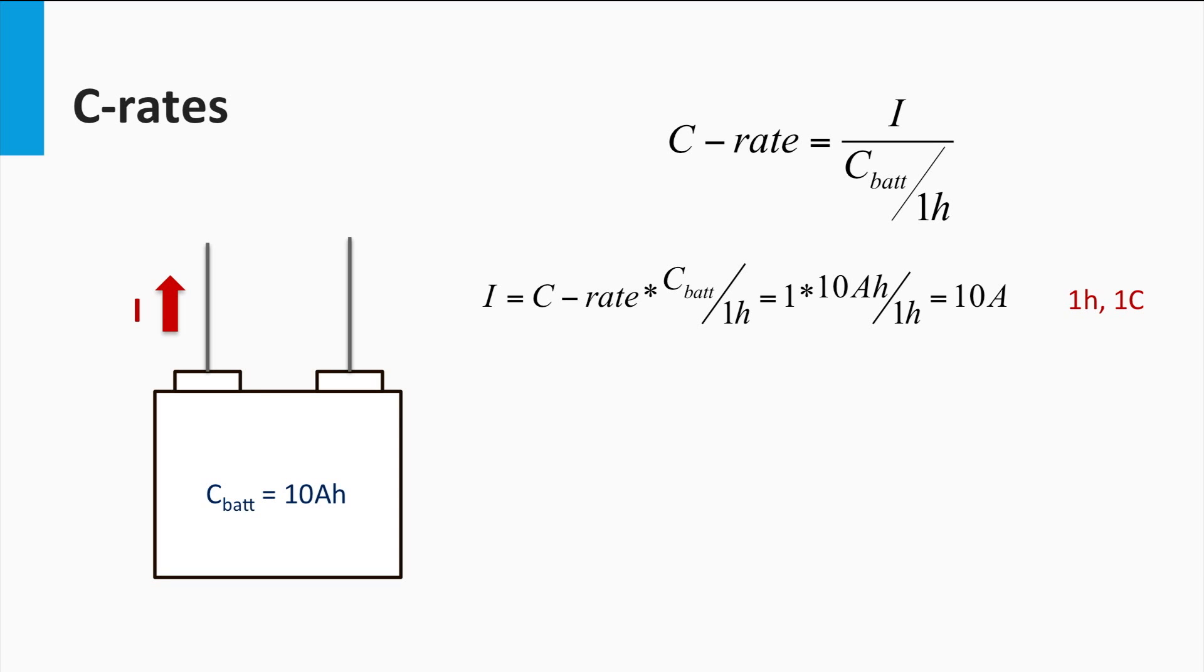This is where the C-rate comes in. C-rate is a measure of the rate of discharge of the battery relative to its capacity. The C-rate number is nothing but the multiple of the current over the discharge current that the battery can sustain over 1 hour. For example, a C-rate of 1C for a 10 Ah capacity battery would correspond to a discharge current of 10 A over 1 hour.